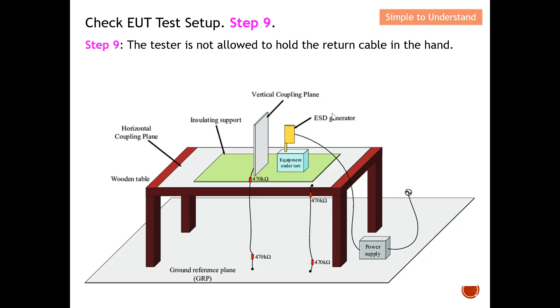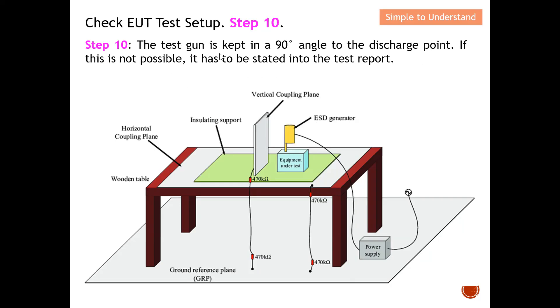Step number ten: the test gun must be kept at a 90-degree angle to the discharge point. If this is not possible, it must be stated in the test report. These are all 10 steps to ensure your ESD test setup is fully compliant with the standard.